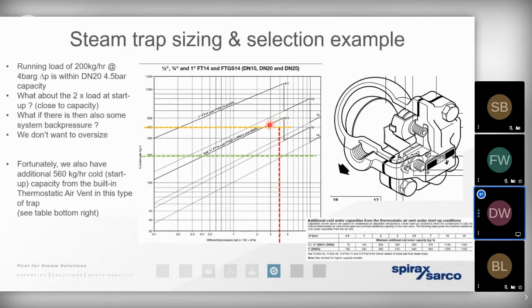So if we look where the orange line and the red line intersect, that shows us how we've now correctly sized and selected the appropriate steam trap. On this occasion, it's what we'd refer to as an FT14 4.5. The 14 is essentially representative of the maximum pressure rating of the casting, and the 4.5 tells us the acceptable differential pressure.